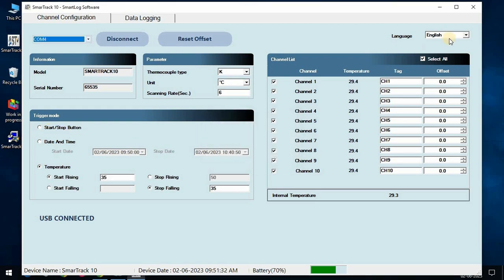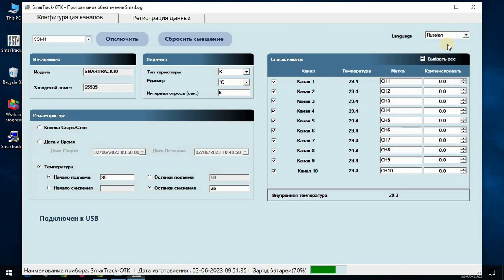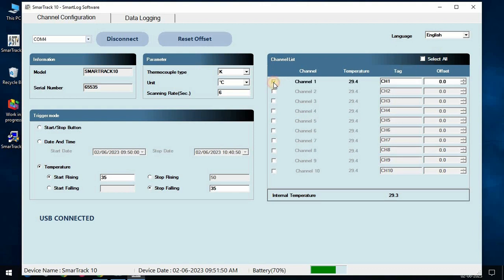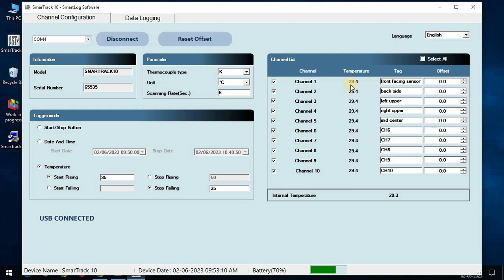We have the option of switching languages between English and Russian. From the channel list tab, we can select all the channels same time or an individual channel as per the requirement. Channel list shows channel number, its temperature, and we can give any name to the channel based on requirement. We can also use this offset feature to correct our temperature readings.